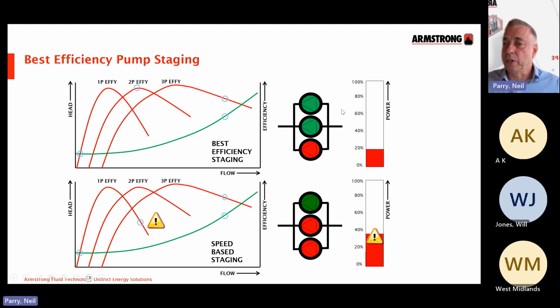And you can see that what the result is, running 2 pumps at their best efficiency point requires less power than running a single pump at a higher speed and a lower efficiency point, much higher pump energy use there. It's called best efficiency staging. It's built into our pumps, and 4 pumps can communicate between each other to make sure they're all running at their best efficiency points.